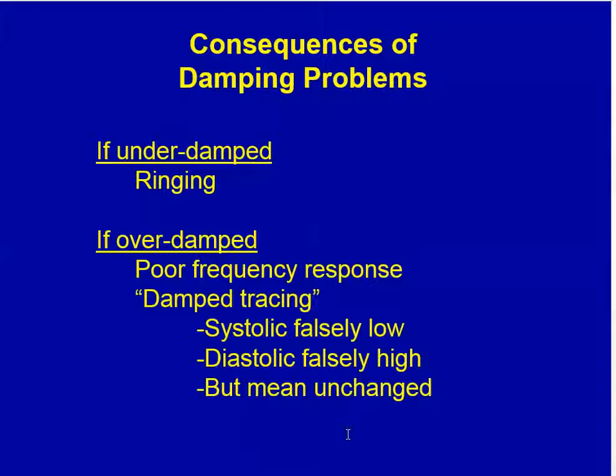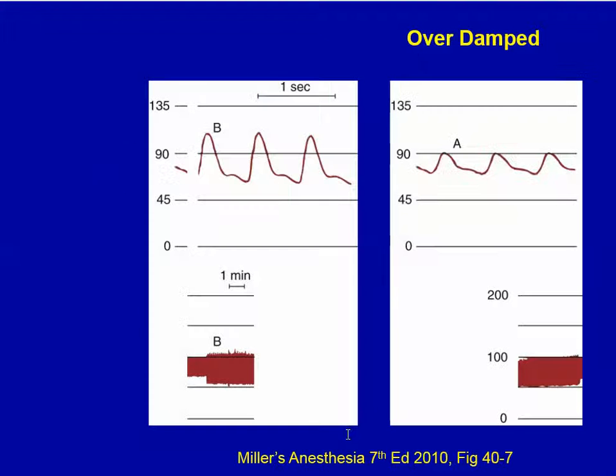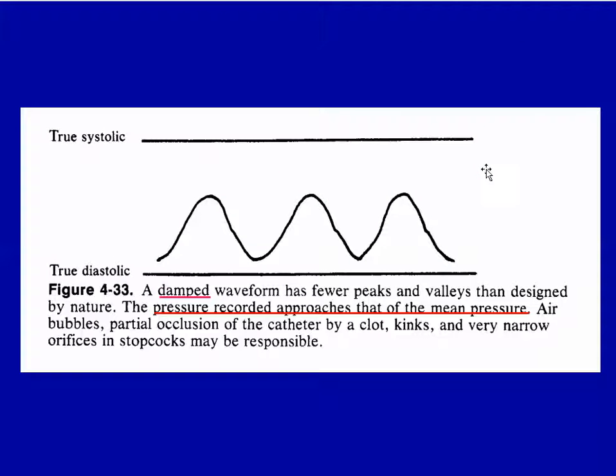If the system is under-damped you get ringing, and if it's over-damped you get poor frequency response — systolic pressure is falsely low, diastolic pressure is falsely high, but mean arterial pressure should be unchanged. Here is an illustration of a properly damped system versus an over-damped system, showing that displayed systolic is lower than true and diastolic is higher than true, but the mean is about the same.